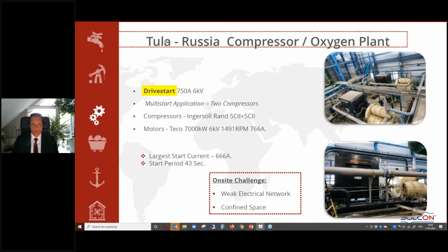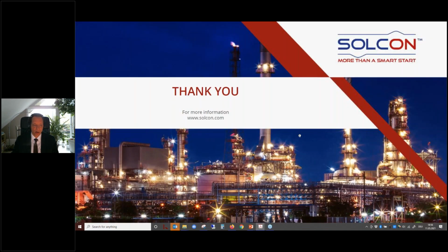And one other application was, for instance, here in Russia for a compressor for an oxygen plant, 7 megawatt motor, 760 amp, and we needed a relatively high starting current. Starting period was 43 seconds, and motivation for this was, on the one hand, a weak electrical network, but also confined space, and with our product, we could really fit into that confined space, and drive start was here the right solution.